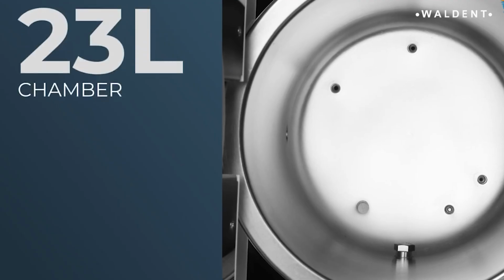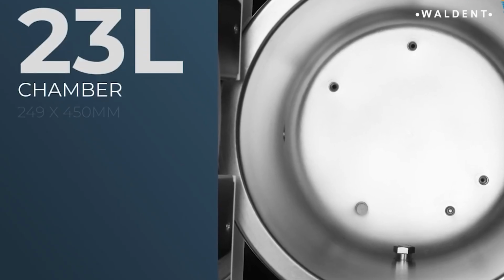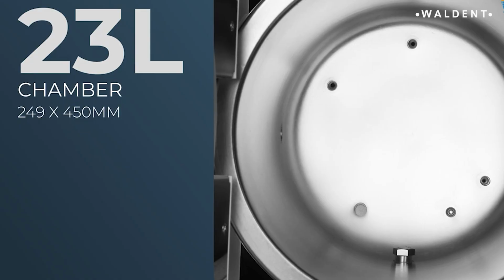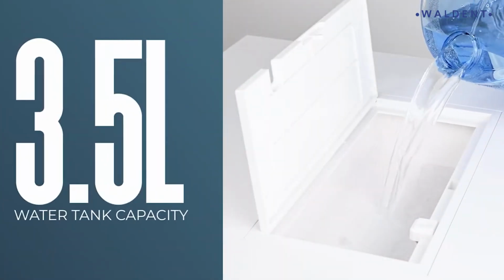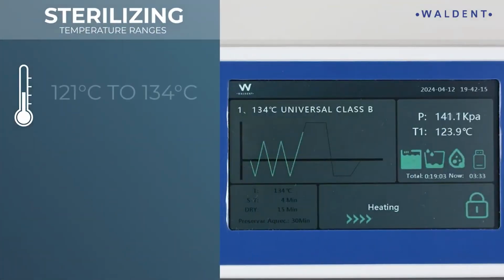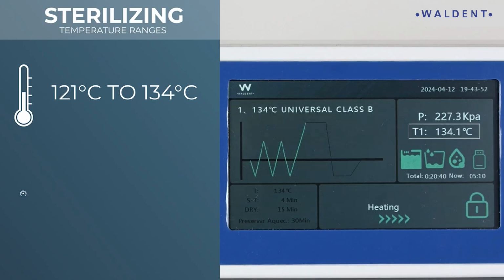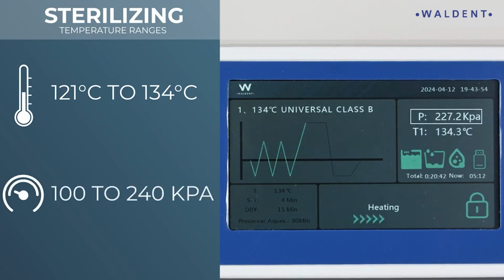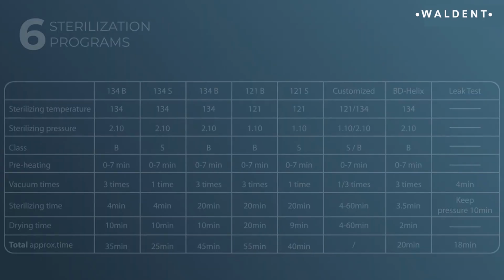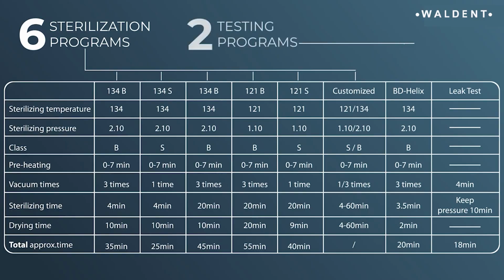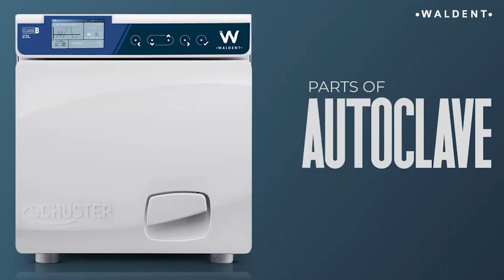It has a 23-liter chamber with inner dimensions of 249 by 450 mm and has clean water tank capacity of 3.5 liters. The sterilization temperature ranges from 121 degrees Celsius to 134 degrees Celsius, and the sterilization pressure ranges from 100 to 240 kilopascals. Waldent Schuster Autoclave has 6 sterilization programs and 2 testing programs, allowing for a versatile range of applications. Now we'll see different parts of this autoclave.